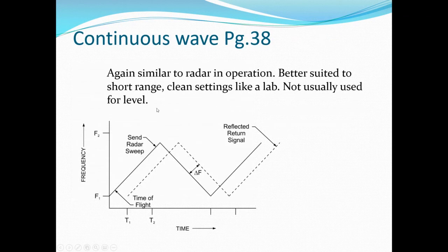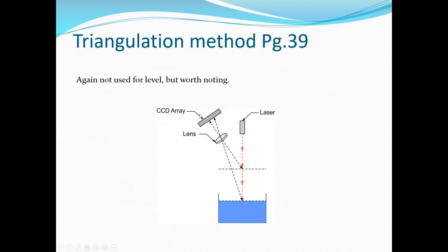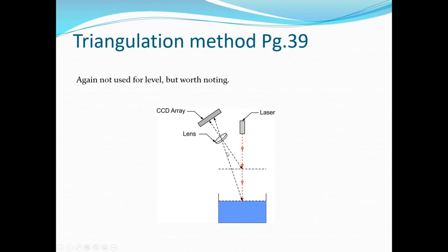Continuous wave lasers operate very similarly to radar — better suited for short ranges and clean settings like a lab, not typically used for field level measurement. The triangulation method uses an array of several detectors in one housing. As the level goes up and down, it changes the angle of reflection, focusing the beam on different sensors — giving quarter, half, three-quarters, full type readings.